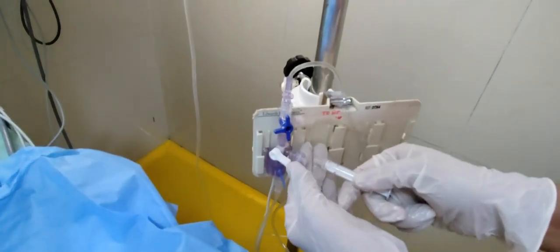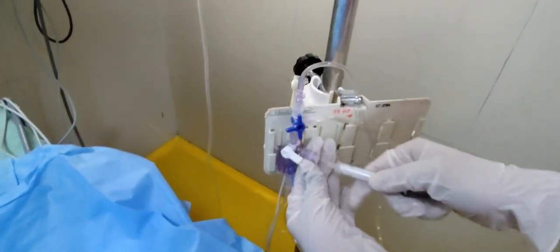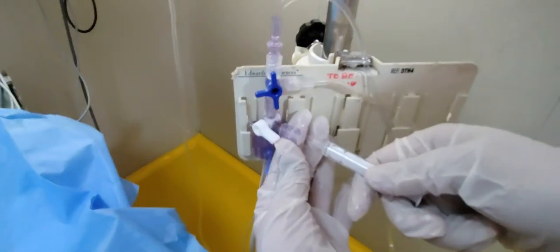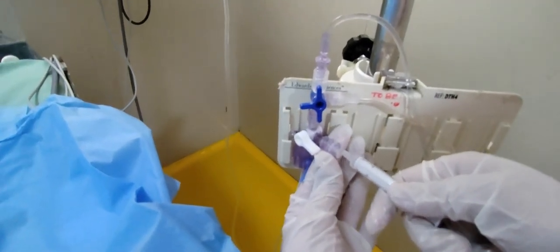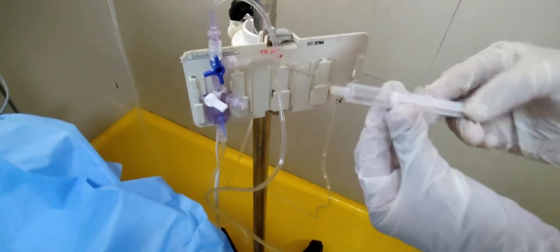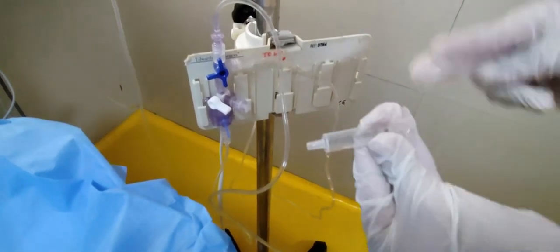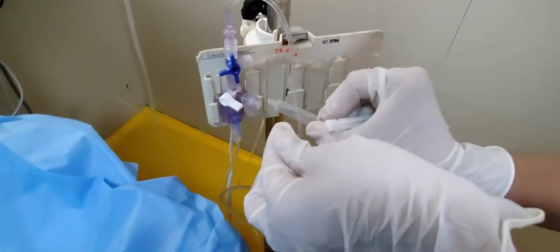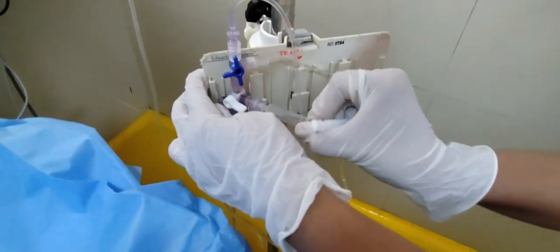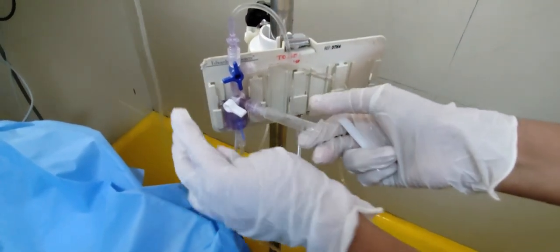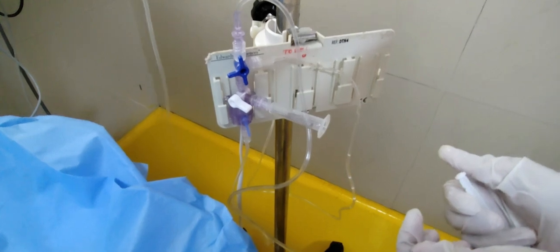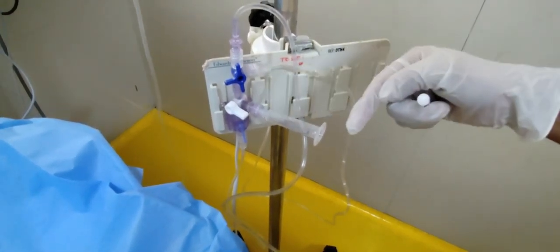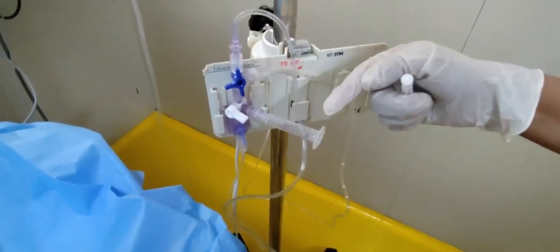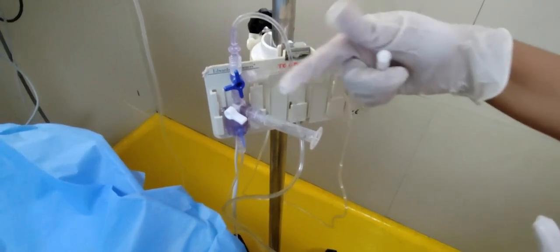If we have to do a repeat zeroing, because this is not open to the atmosphere for equilibrating, you can use a syringe with the plunger removed and connect it to the hub, so that this is open to the atmosphere and it enables zeroing by equilibrating to the atmospheric pressure.